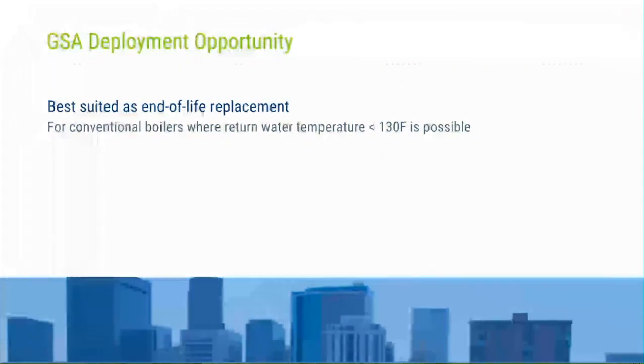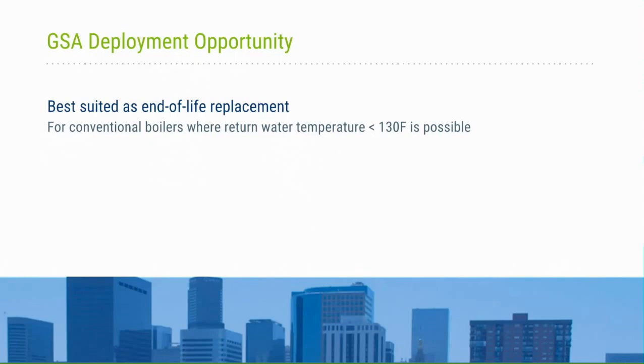So the takeaway that we saw is these are really well suited as end-of-life replacements, but it's key to look at not just the boiler selection, but your larger building environment, and whether that building lends itself to getting these low return water temperatures back, or easy retrofits to enable that. So they really showed good economic performance and good technical performance, especially in these conditions. Next slide.